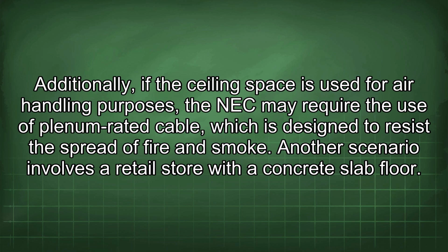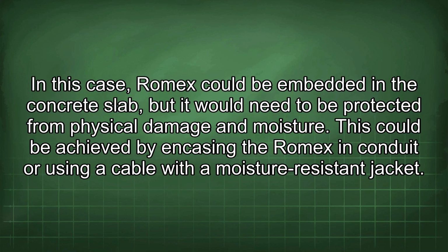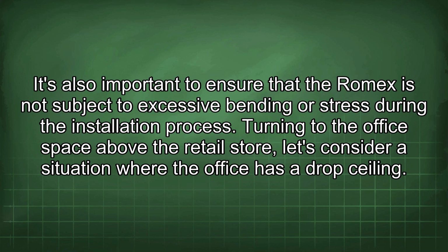Another scenario involves a retail store with a concrete slab floor. In this case, Romex could be embedded in the concrete slab, but it would need to be protected from physical damage and moisture. This could be achieved by encasing the Romex in conduit or using a cable with a moisture-resistant jacket. It's also important to ensure that the Romex is not subject to excessive bending or stress during the installation process.